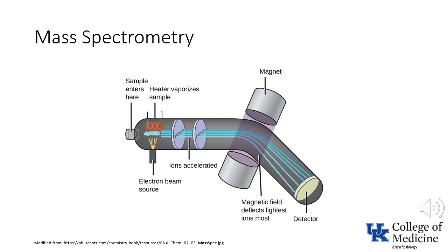Mass spectrometry is capable of determining the concentration of volatile anesthetic agents as well as respiratory gases. Initially in clinical practice, one device would serve several rooms — if ten rooms were connected, your room would only be monitored ten percent of the time. Later, infrared capnometers were added alongside the mass spectrometer, with an infrared capnometer in each room so real-time measurements could be performed at each location.